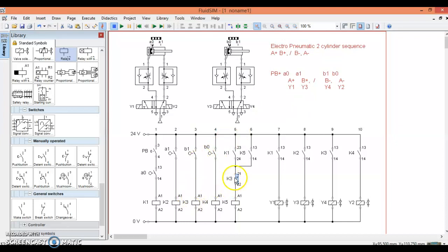When K3 comes on, this normally closed contact will open, K5 will go off. So now we've got a relay that is coming on here and going off here. We can then use it to interrupt certain elements of this sequence.